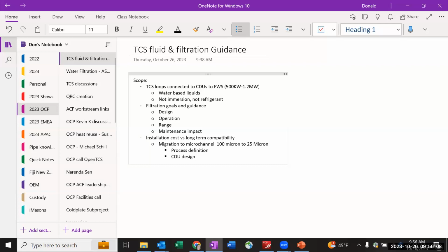So you have to go back and clean out your fluid, maybe just dump the fluid, put in new fluid, and change the filter at the CDU. If the pump assembly was designed to work in a 25 micron environment and would accept a better filter, then you could put a new filter in, exchange the coolant, and I'd let it run for a bit before putting the microchannel server in.